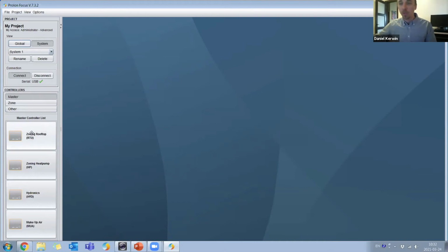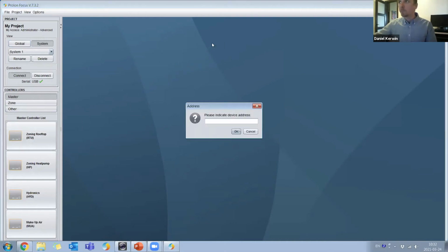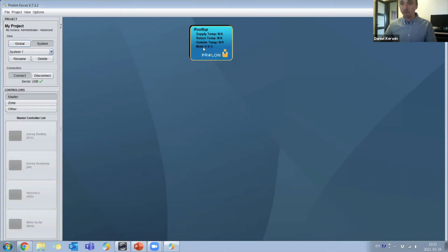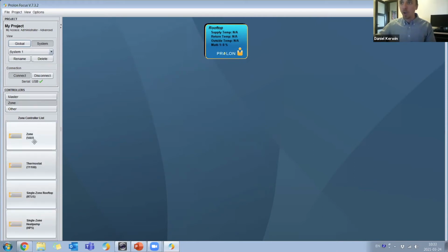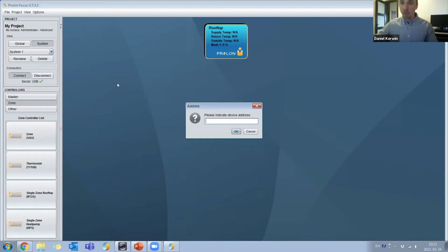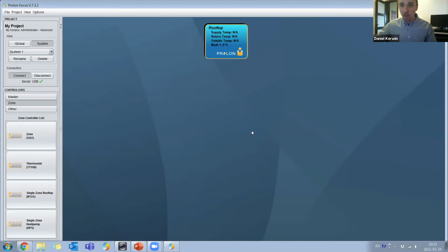On my demo board I already have a rooftop controller, so I'll drag and drop it in, and it asks for the address. I'll put address number 20, and the rooftop pops up right away. I also have 2 VAV controllers on my demo board. I could drag and drop those in and set addresses too, but to be quick and efficient, we can discover all these zones automatically as long as they've already been addressed. I just right click and there's an option that says 'get list,' so I'll click on that.